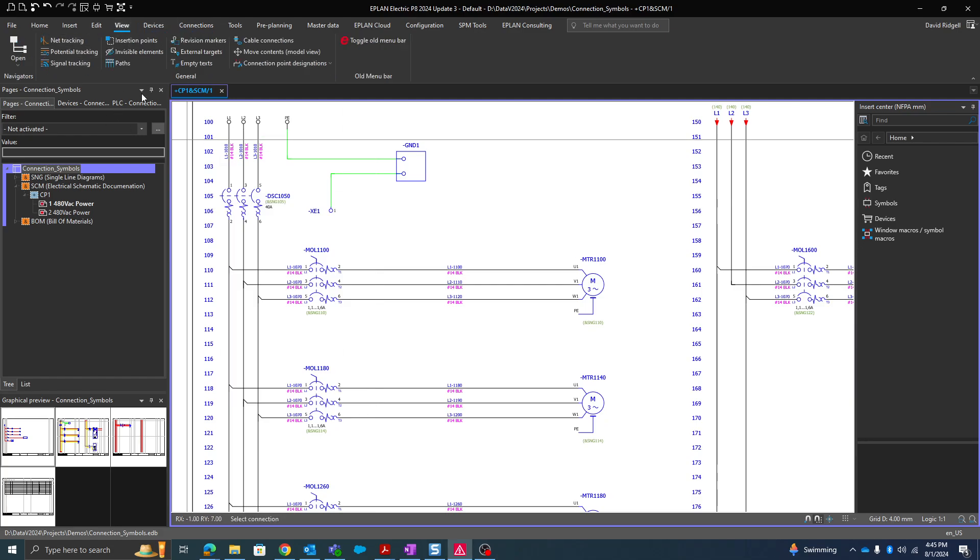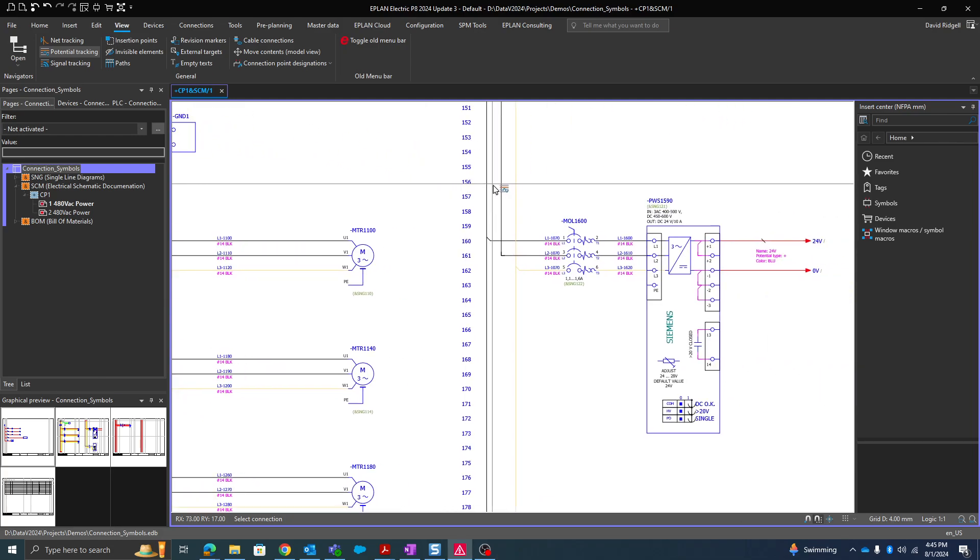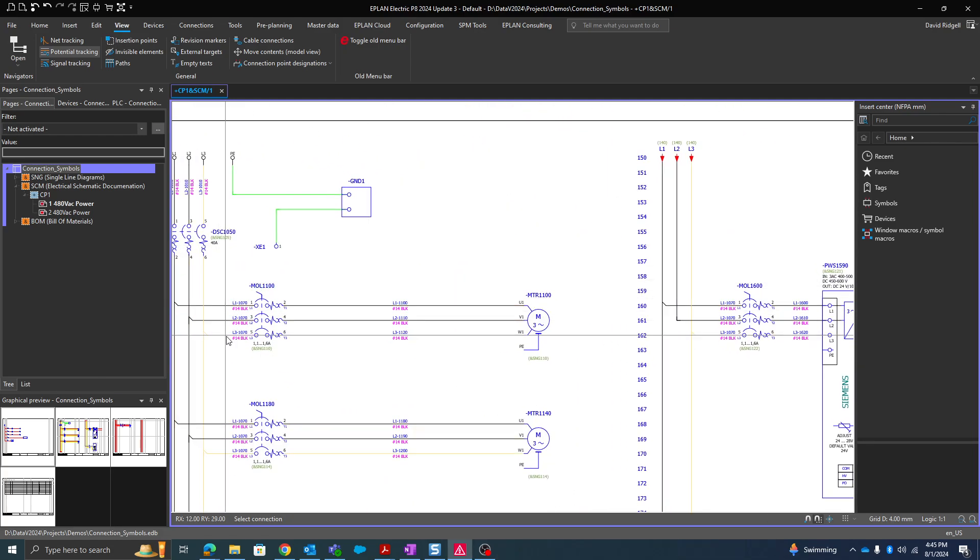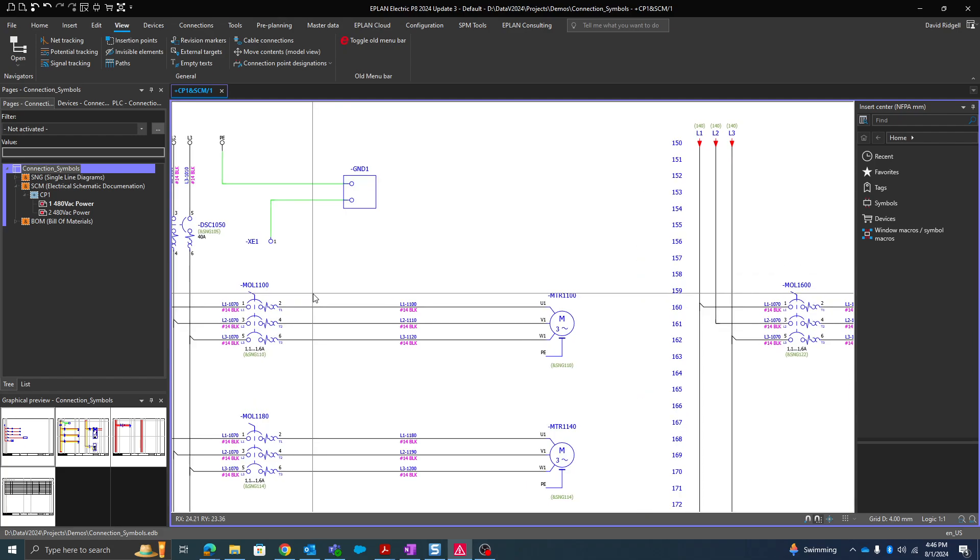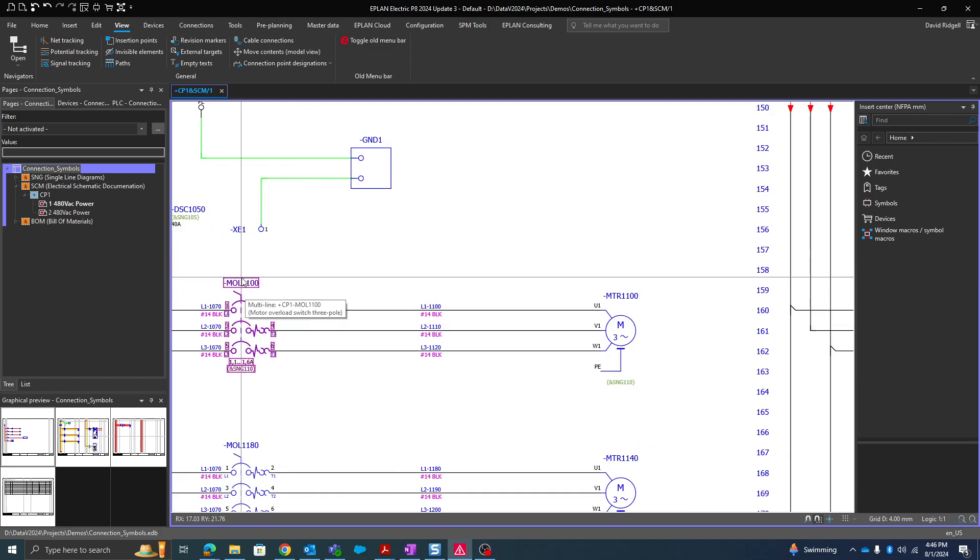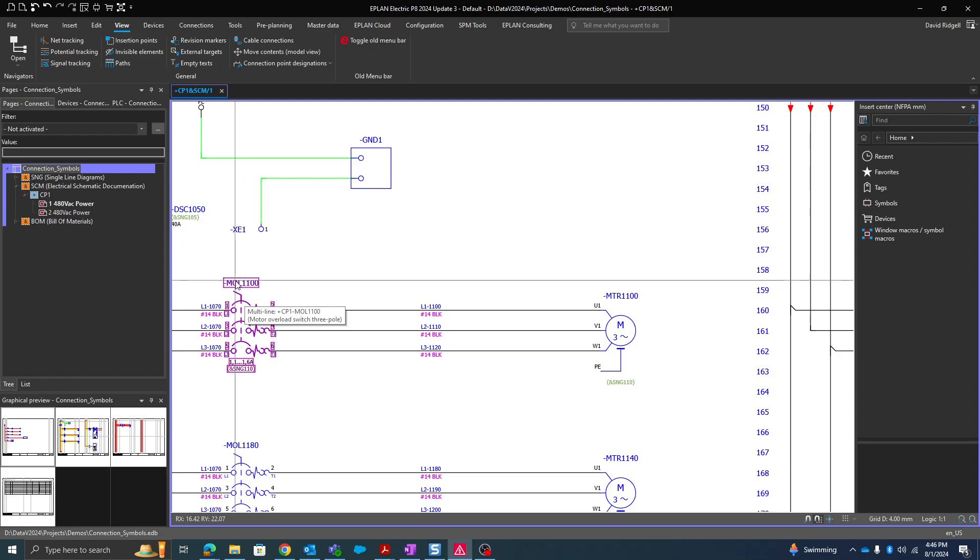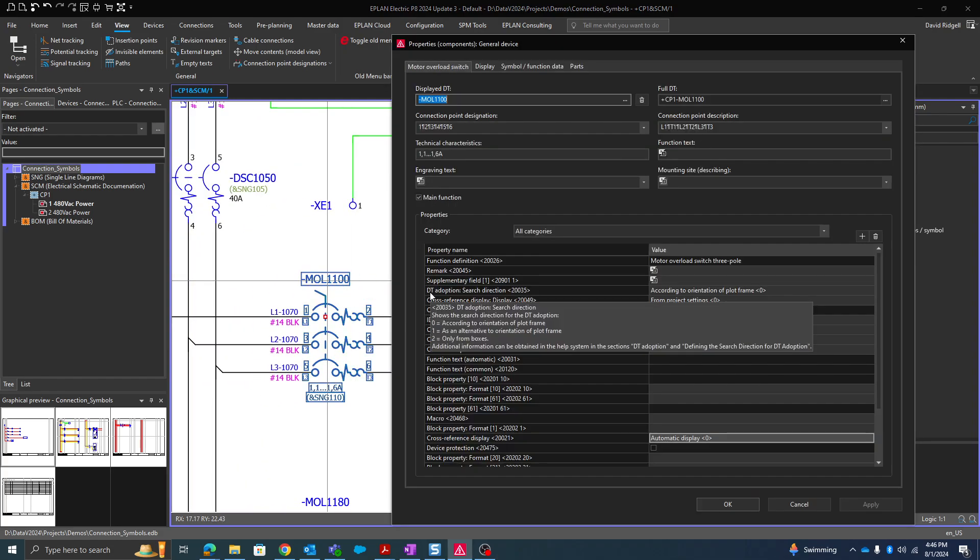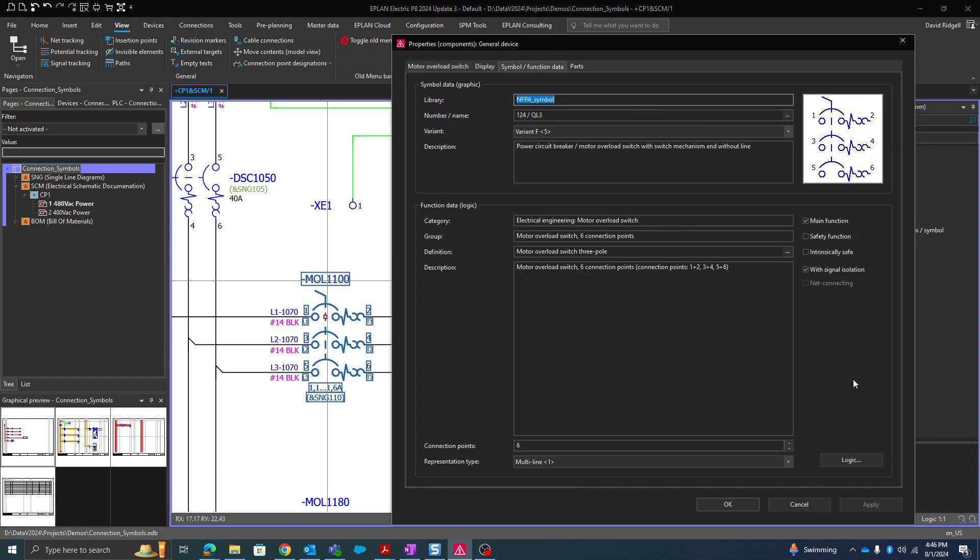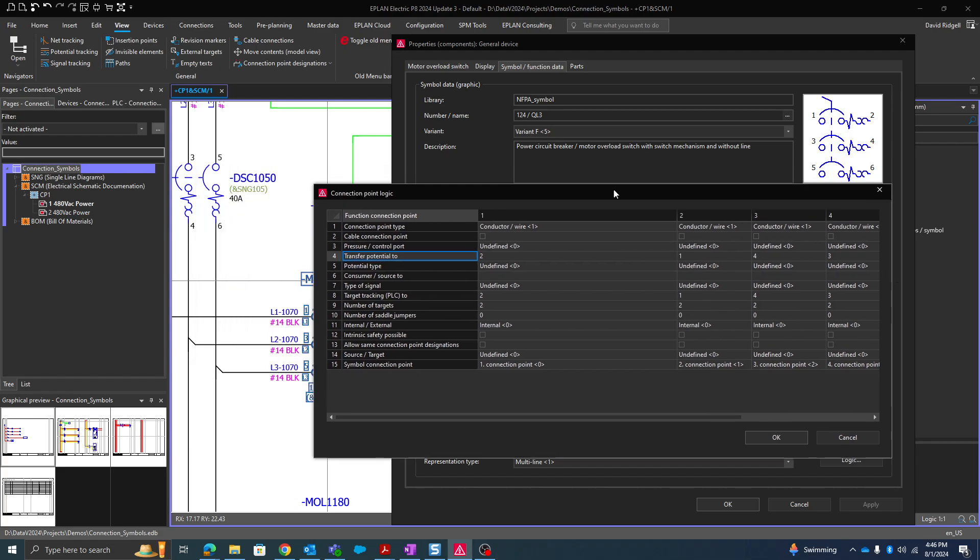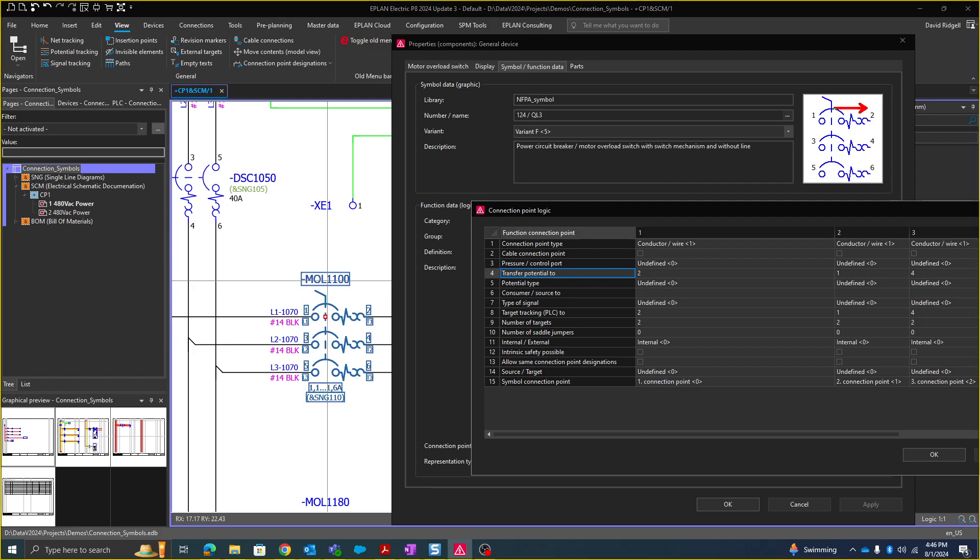You can track your potentials by using the potential tracking. The question is how do we set up this potential transfer? So it's very simple for basic symbols like this motor overload or this breaker. If we go to symbol function data and go to the connection logic, we have a line here for transferring the potential to. So I'm telling connection point 1 to transfer to 2 here.